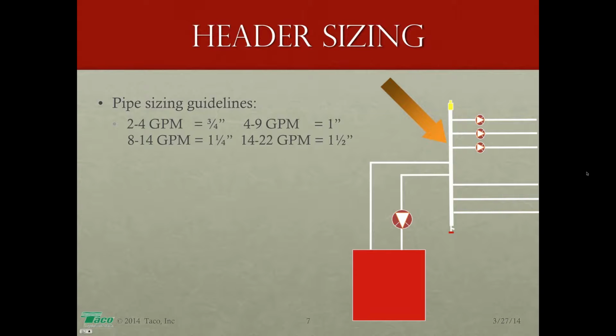Can you oversize the boiler loop? You've got to keep pressure up in the boiler. When they say it should be a minimum of 1 inch, if you went up to 1.5 inches, I'm sure it would be okay. It wouldn't hurt anything. It wouldn't be a major issue. However, you don't want to get too oversized because the tappings on the boiler are going to be 1 inch anyway. So you don't really need to oversize. There's no benefit to oversizing the boiler loop. Now there may be a benefit to oversizing the header.